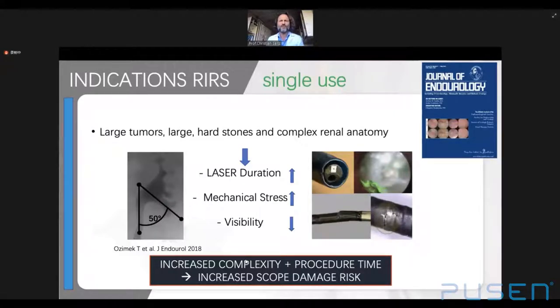Large tumors, large hard stones, and complex renal anatomy lead to longer lasering time, increased mechanical stress, and more frequent instrument failure. A study by Ozimek et al. suggested that a steep infundibulopelvic angle, regardless of stone retrieval complexity, influenced the durability of reusable devices. The vast majority of flexible ureteroscope defects occurred when the measured pelvic angle reached 60 degrees or less. Notably, more than 7% of defects occurred even in diagnostic procedures, meaning the infundibulopelvic angle may play a role in device damage beyond typical lower pole stone cases.